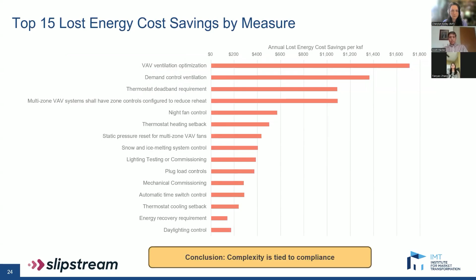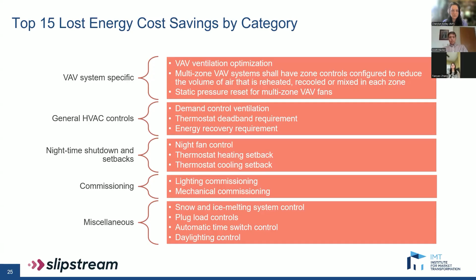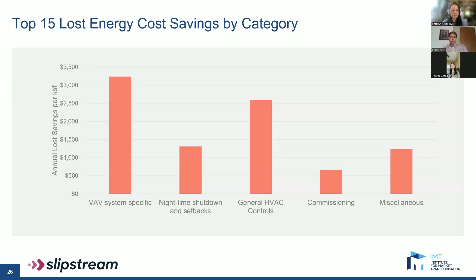So here are the same 15 measures, but categorized into several buckets for easier analysis. This gives us a better picture of the types of measures that are high impact in loss savings. We have them grouped into VAV system specific measures, general HVAC control measures, nighttime shutdown and setbacks, commissioning, and finally miscellaneous measures. So we summed up the loss savings per square foot in each bucket to come up with this graph, just to see the impact by measure category. And it's pretty clear that there's a lot of potential for improvement in VAV system design and operation, as well as general HVAC controls.